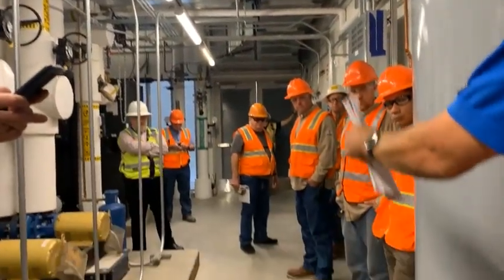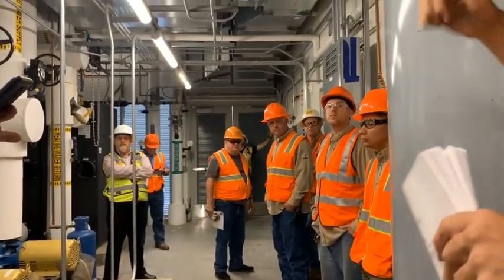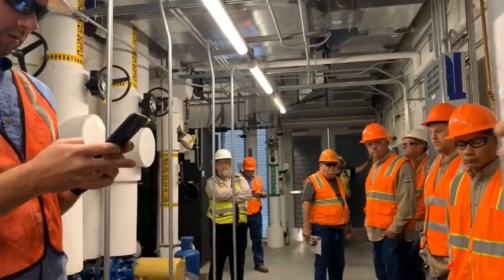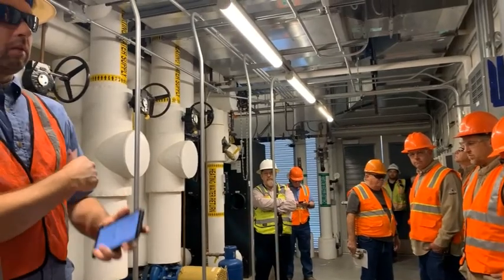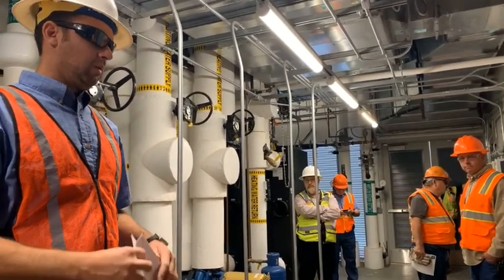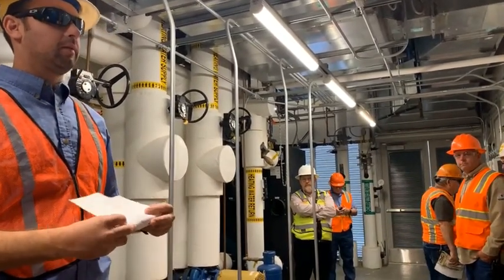And then once everything is buttoned back up here, the drain valve is closed, then you can slowly, anytime you operate a valve, right, we open it slowly, we don't ever slam open a valve or slam it closed, okay? If you slam it closed, you could create water hammer. If you open it too quick, it's just bad.